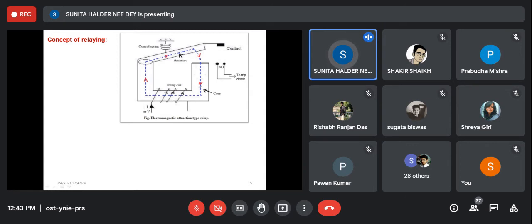Then what will happen? Due to the energization of this relay coil, as per the direction, this type of flux will be produced. Which side will be the north pole? Here flux is coming out from here, so this side will be the north pole, and this side will be the south pole. Now if the current is high enough, then the flux will be strong enough, and this air gap between the moving part and the fixed part is very small. So actually this moving part will move towards the south pole. This is the moving part, I may write here M, and this is the fixed part.